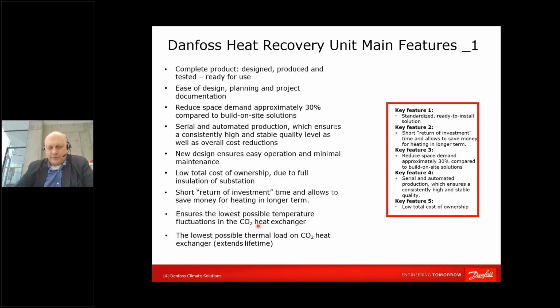leading to fluctuation of the temperatures, up, down, and if you would like to bend something and try to break something, you would eventually break it. That happens with a CO2 exchanger. If it's getting high temperature, high pressure on one side, and suddenly cold water on the other side, it is stressed all the time. It's working like a harmonica or something, I don't know how to call that musical device, but it's stressed every time.